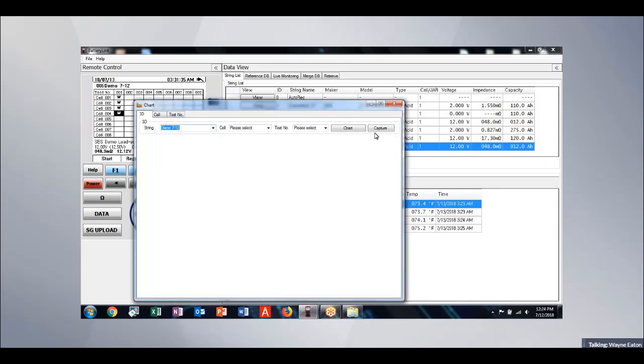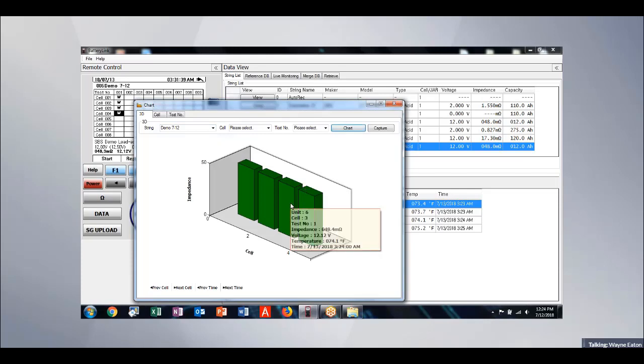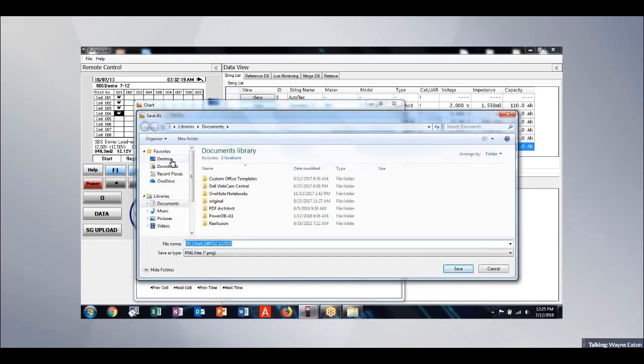So if I come down here and I hit chart, I can chart the historical trends of that battery by cell or by string over the life of the battery system as well. And these bar graphs are color coded as well to show the changes from normal readings to warnings to failures. I can look at an individual cell and just look at cell number 1 and chart its history. Or I can look at a particular test and chart that entire test. From here, I can also do a screen capture if I wanted to incorporate that into a report. Just throw that on the desktop.